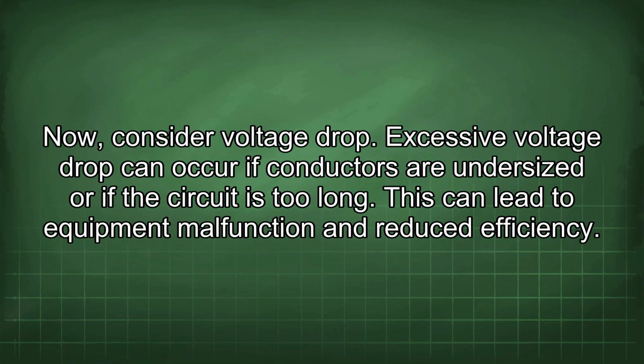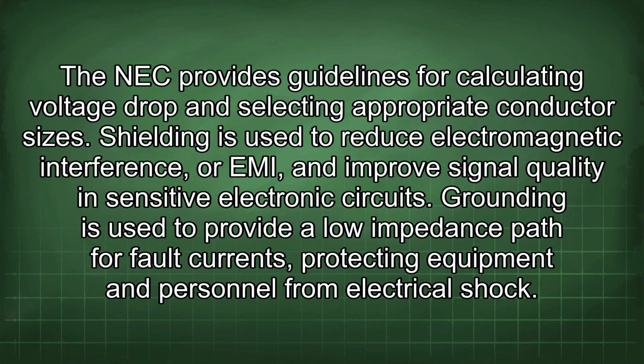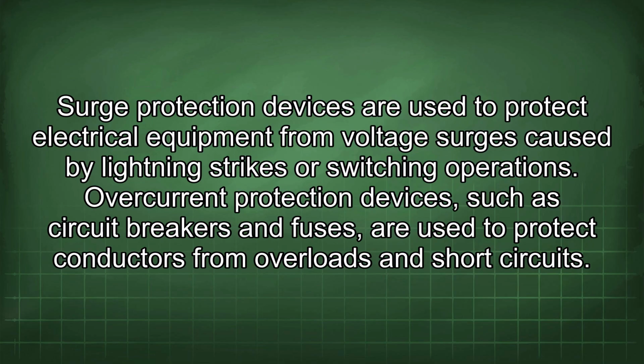Now consider voltage drop. Excessive voltage drop can occur if conductors are undersized or if the circuit is too long. This can lead to equipment malfunction and reduce efficiency. The NEC provides guidelines for calculating voltage drop and selecting appropriate conductor sizes. Shielding is used to reduce electromagnetic interference, or EMI, and improve signal quality in sensitive electronic circuits. Grounding is used to provide a low impedance path for fault currents, protecting equipment and personnel from electrical shock. Surge protection devices are used to protect electrical equipment from voltage surges caused by lightning strikes or switching operations. Overcurrent protection devices, such as circuit breakers and fuses, are used to protect conductors from overloads and short circuits.